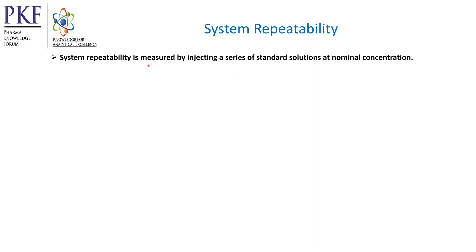System repeatability is measured by injecting a series of standard solutions at nominal concentration, and it depends upon the method. For a purity test by area normalization method, the standard will be injected at nominal concentration. For repeatability test of impurity profile, the corresponding impurity at a specification level will be injected. For system repeatability of assay test, the standard will be injected at nominal concentration.